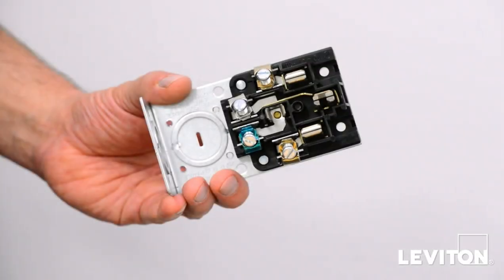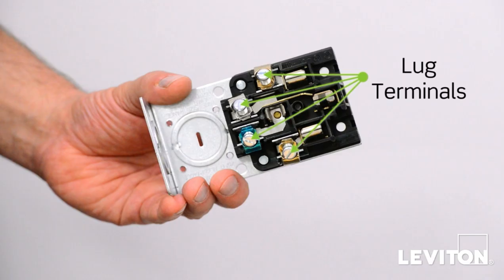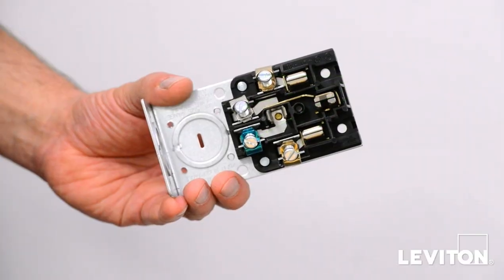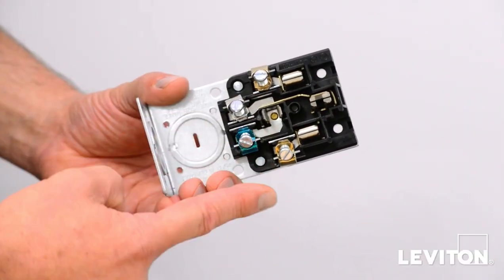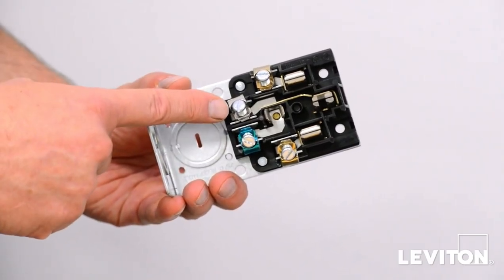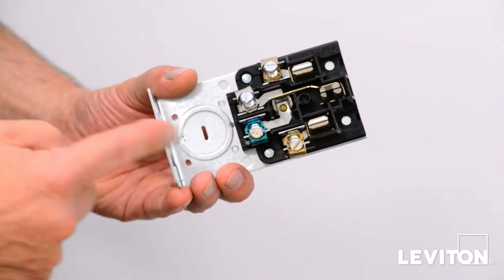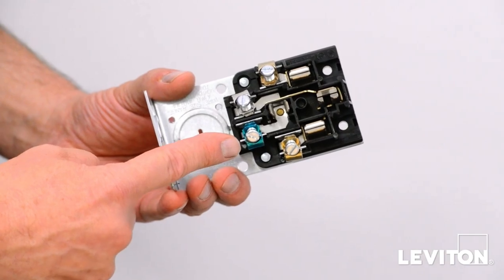The terminals located on the back of this receptacle are referred to as lug terminals. These type of terminals are typically presented on devices that permit a larger size wire gauge conductor. The brass terminals labeled X and Y are for the hot wires. The silver terminal labeled white is for the neutral wire and the green terminal labeled green is for the ground wire.